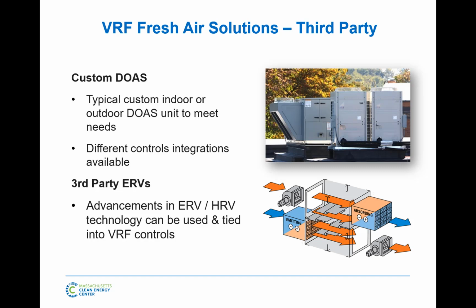Then there's the custom world. Again, if you're more in the HVAC industry, the more you get into applied buildings, larger buildings, you get to the custom world. So where this ties into our discussion today is that if you want to do a custom roof-mounted energy recovery unit, a custom roof-mounted air handler, a custom DOAS unit, which is a big percentage of the market, you can do that and tie any of those to a VRF condensing unit. So that will happen now. It's like, I'm doing a whole building.